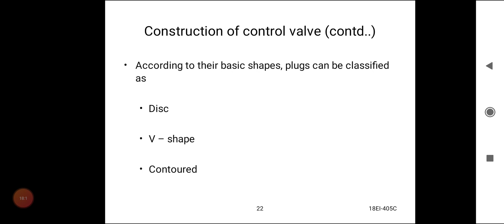Here there is a seat. The plug is connected to this stem and pinned. Valve plug, quick opening type. Valve spindle, that is the stem. Spindle movement is a linear movement in either direction, opening or closing the valve. Orifice pass area. This is a linear plug which is sitting on the seat.